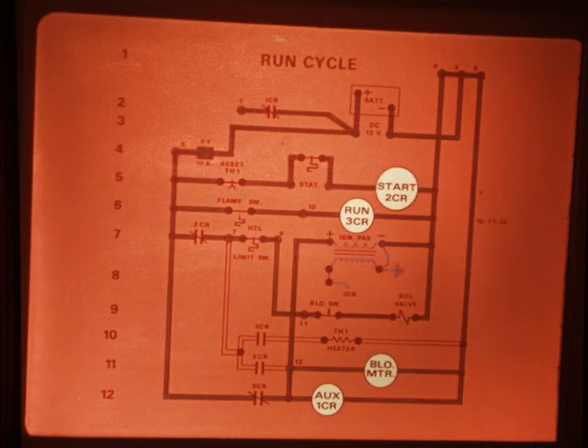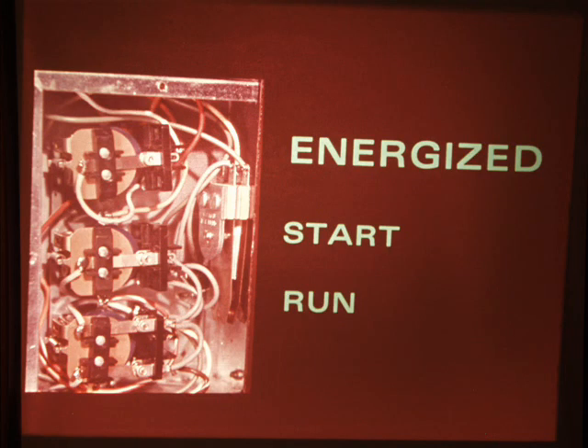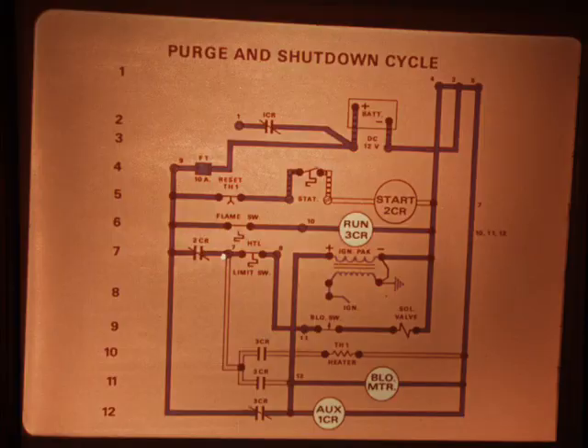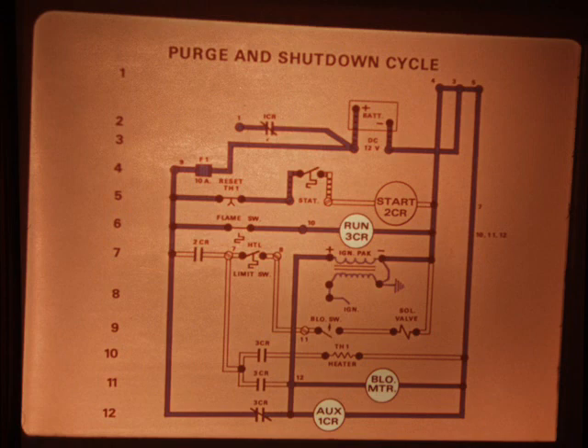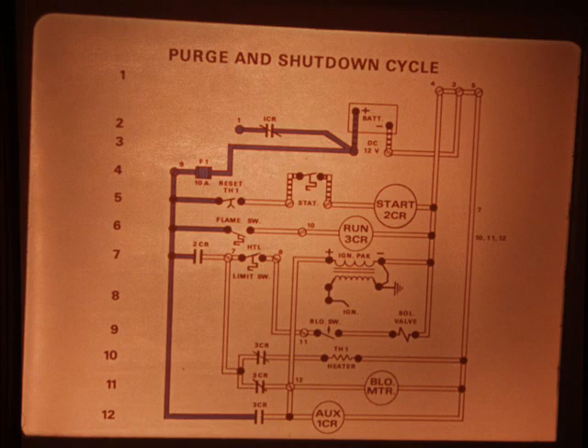When the run relay is energized, power is cut off to the thermal reset heater, but continues to the blower motor through a set of normally open contacts. For the furnace to operate on normal run, both the start and run relay must be energized. Now, when the temperature in the coach builds up and the thermostat opens, the furnace goes on the purge cycle to cool the heat exchanger. So the start relay is de-energized, and this cuts off power to the solenoid on the gas valve. The blower, however, continues to run as long as the run relay is made. Then, when the flame rod cools, it opens the circuit to the run relay and shuts the blower down. And that's the normal furnace cycle.